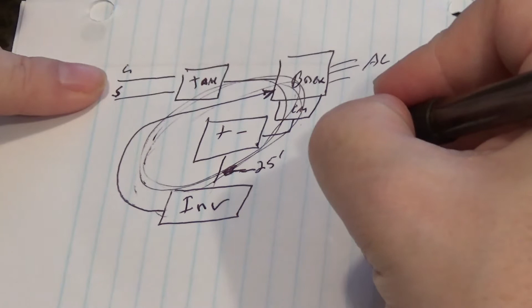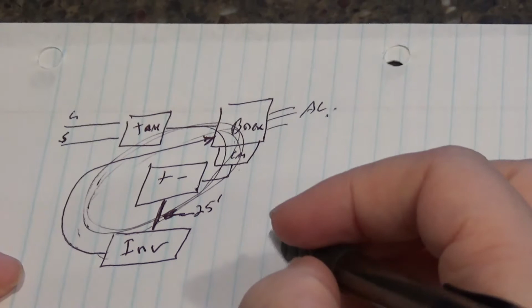And the batteries and the inverter were probably, as the crow flies, 25 feet away, with not a small gauge, but not enough to prevent voltage drop. It's the voltage drop, not the amperage rating.